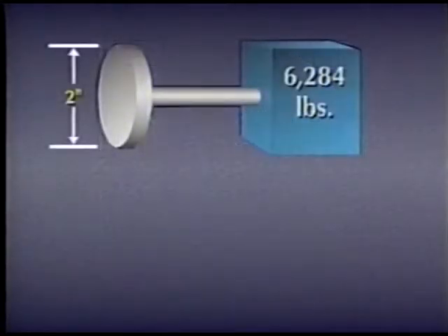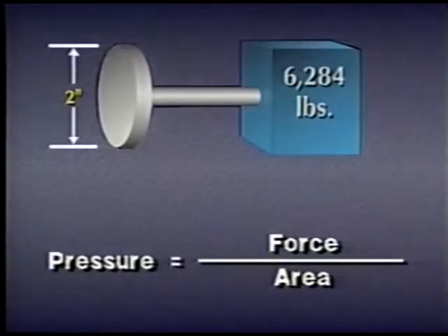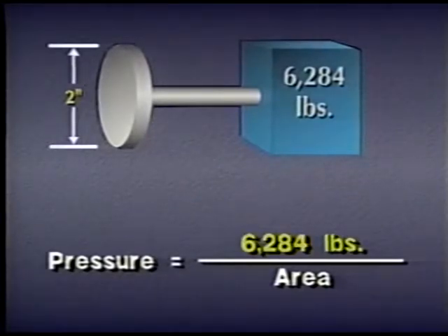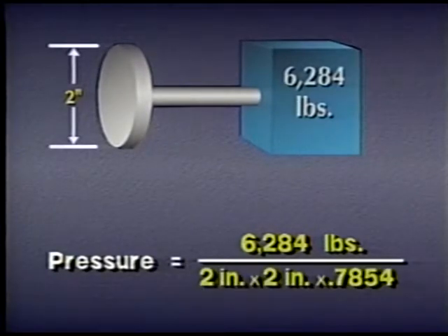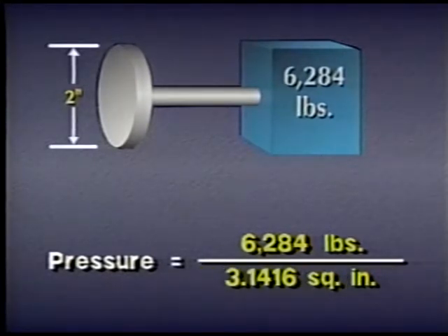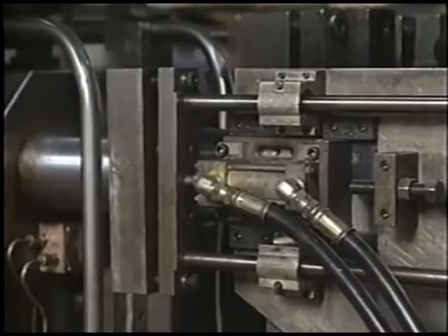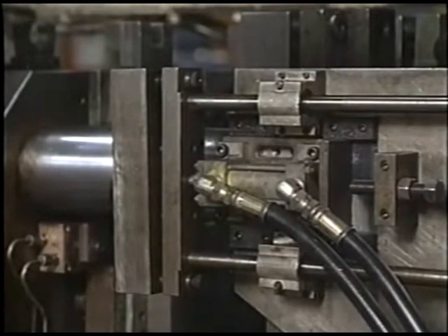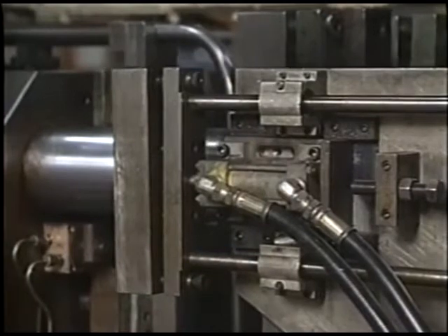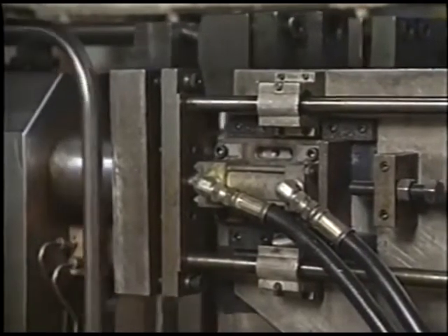For example, suppose we have a 6,284-pound load to be moved by a cylinder with a 2-inch bore. To calculate the pressure required, we divide 6,284 pounds by the area of the piston. That area is 2 times 2 times 0.7854, or 3.1416 square inches. 6,284 divided by 3.1416 equals 2,000 pounds per square inch. To move the load, the hydraulic system must operate at 2,000 psi. In the real world, we also have to account for friction and other inefficiencies, so more pressure would be required.